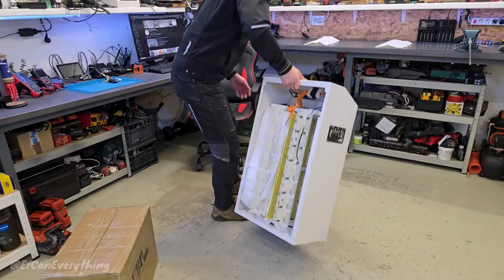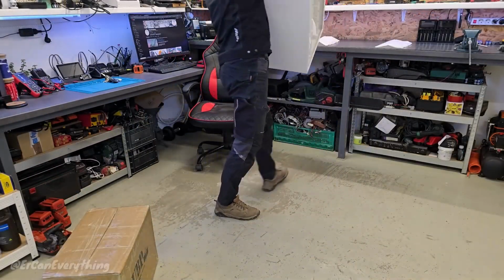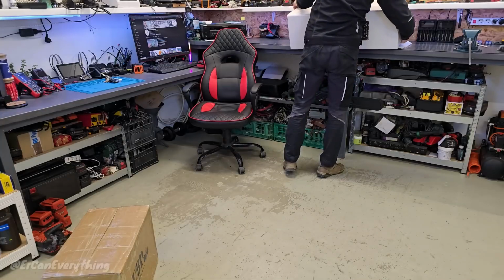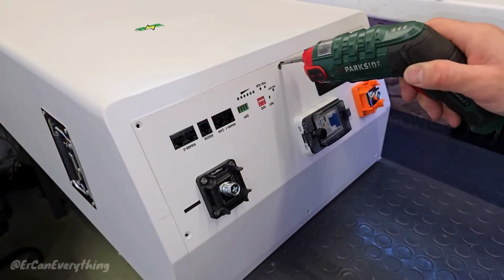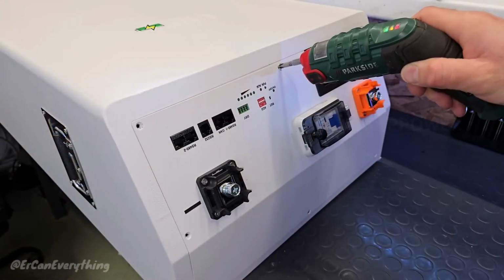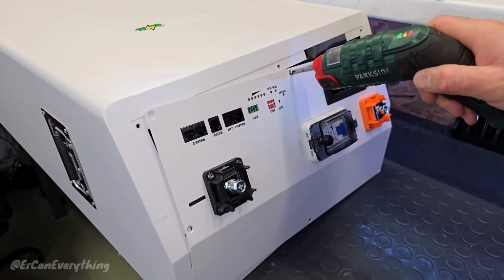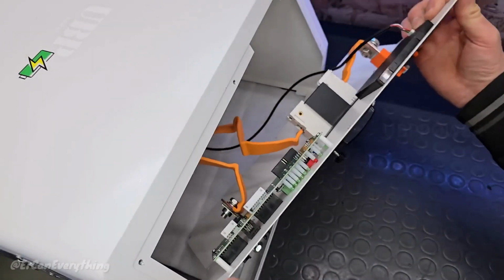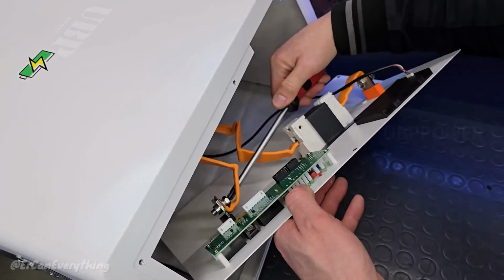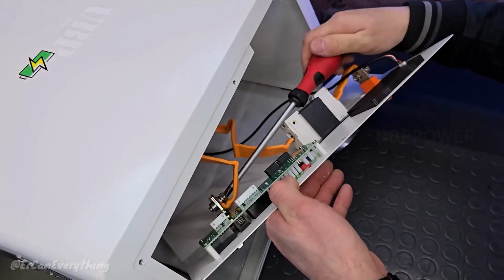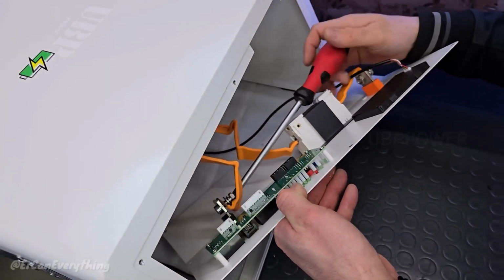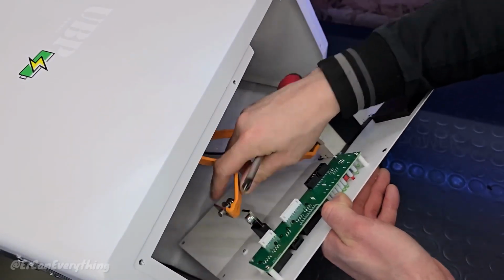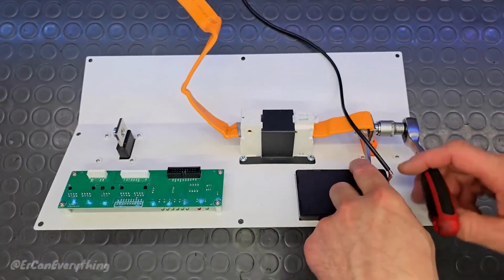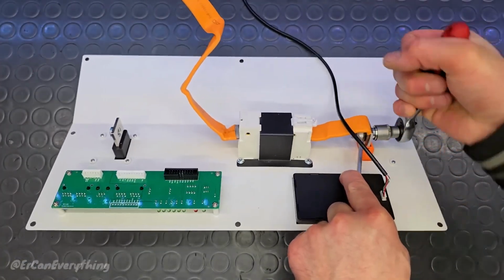Place the battery box on a flat surface, preferably on the ground, in preparation of the battery cell insertion and cable connections. Keep in mind that the battery will weigh approximately 250 pounds when fully assembled. Remove the top cover and check the bus bar connections for tightness. Avoid over-tightening.